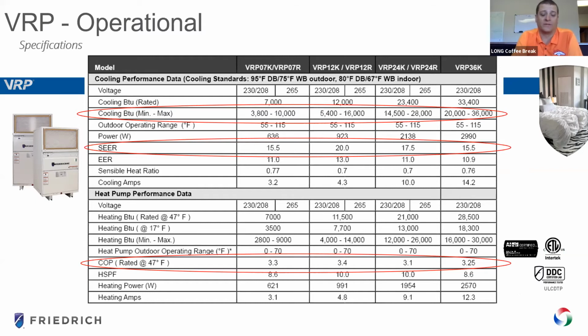And then also kind of, as I was discussing earlier about the electric heat, the COP of most of these units is above 3. So again, you're having that energy savings between 0 and 40 or whenever your typical heat pump cuts out. The VRP unit is still able to continue operating all the way down to 0, and you're getting those efficiencies instead of having to turn on your electric heat.